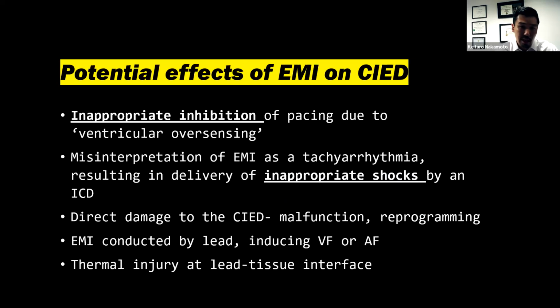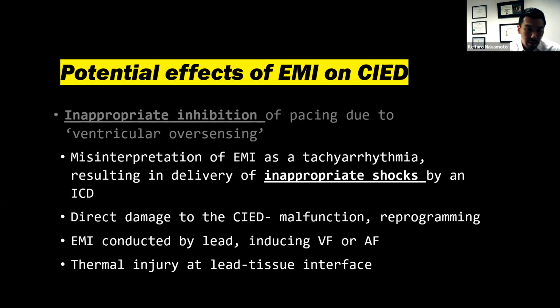So what are the potential effects of EMI on cardiac implanted electrical devices? The most important one is inappropriate inhibition of pacing due to ventricular oversensing. Ventricular oversensing is when the pacemaker senses electrical signals, such as from the Bovie, that should be ignored, and instead interprets these signals as native R waves, resulting in no pacing generated by the pacemaker. This can result in profound bradycardia or asystole in a pacing-dependent patient. It can also cause misinterpretation of EMI as a tachyarrhythmia, resulting in delivery of inappropriate shocks by an ICD. I think these two are the main things that are important.